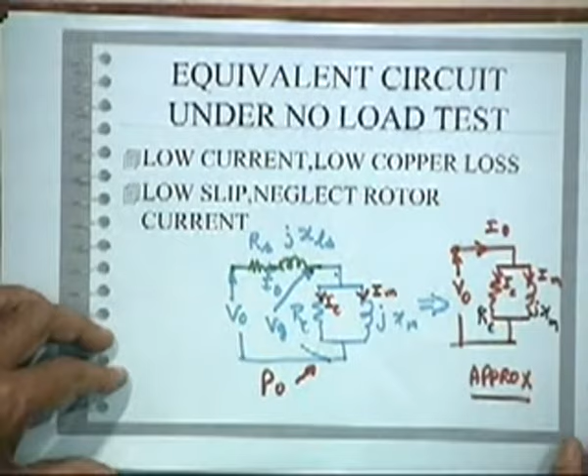Now next we want to know what are the calculations that we do from the no load test. You have taken the reading - you have measured P naught so many watts, you measured V naught so many volts, and you have measured I naught so many amps, that you have measured per phase. So we are starting per phase, because whatever measurement you take may be line, but you have to convert into per phase depending upon the type of connection that is made.